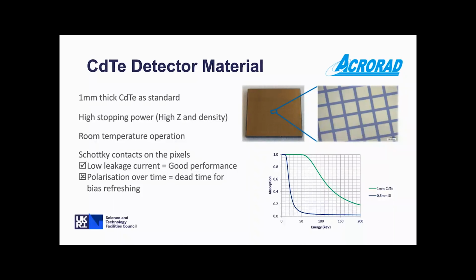And we use this material because it's got a high atomic number and a relatively high density. So that just means it's got lots of electrons, and those electrons are going to stop the X-rays when they're interacting with the material. You can see at the bottom there, compared to silicon, it's got a much higher stopping power. So at 100 keV, it's stopping around 65% of the photons incident on it. It operates at room temperature as well. So we always operate HEXITEC at room temperature.